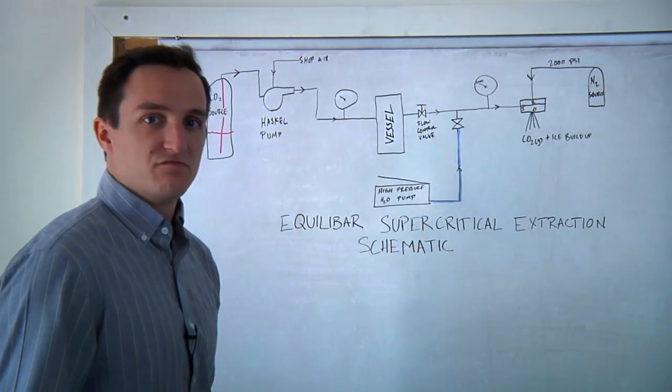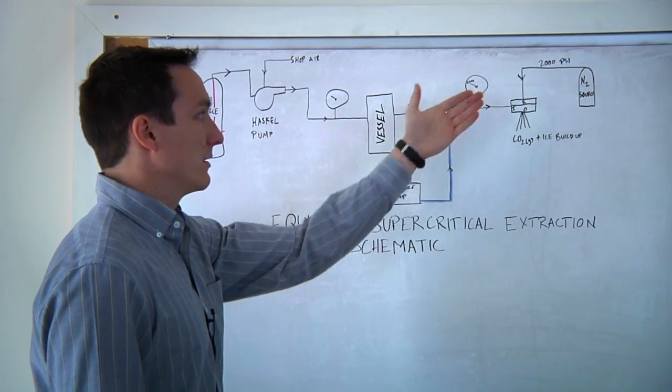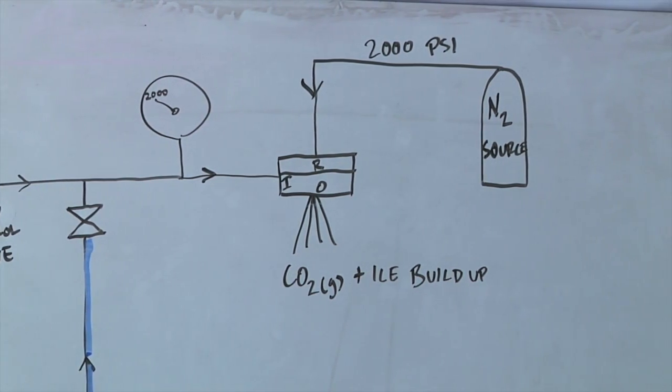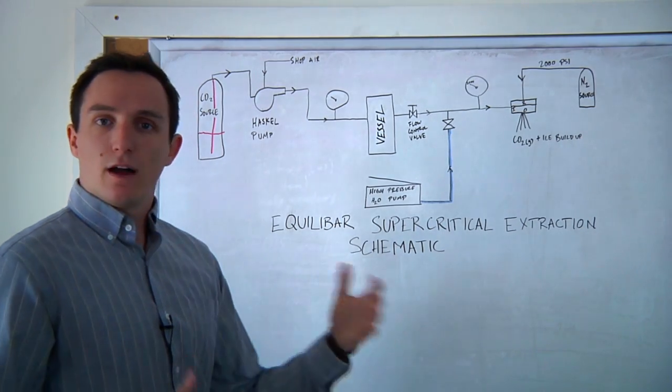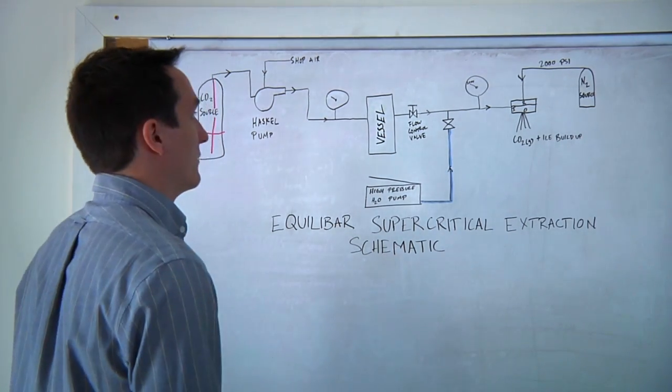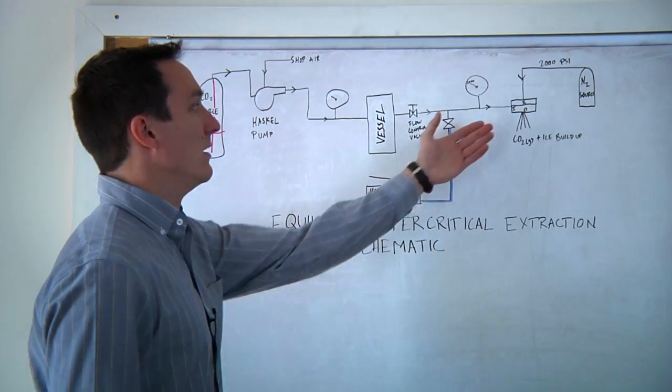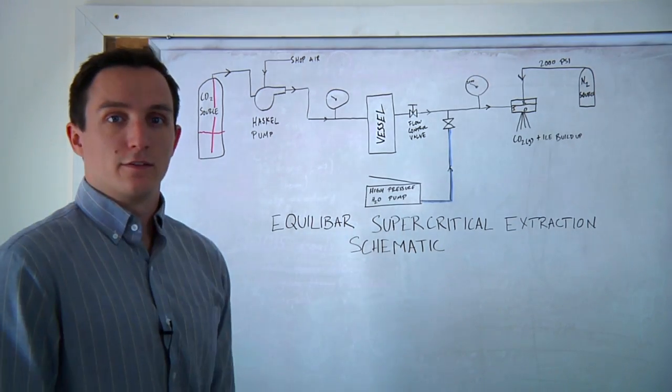Our regulator is just like any other Equilibar Research Series regulator. It has a reference port, an inlet port, and an outlet port. The reference is typically piloted by a nitrogen source, although you can use high pressure air or any sort of high pressure gas source. That's the way we typically ask you to pilot the regulator, and then the outlet, which we have several different options, which I'll outline at the end of this video.